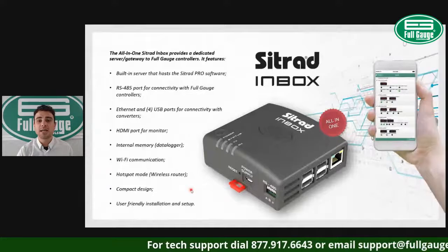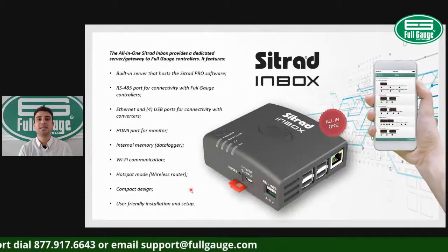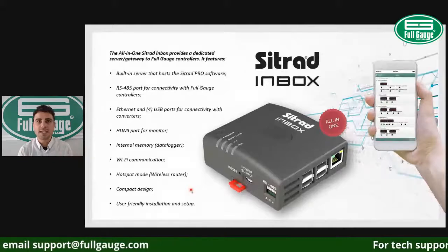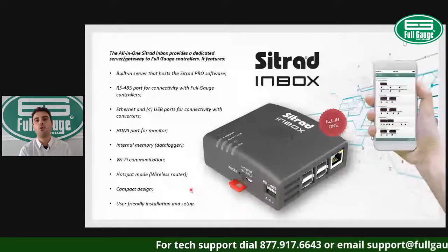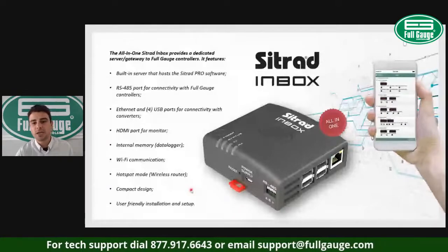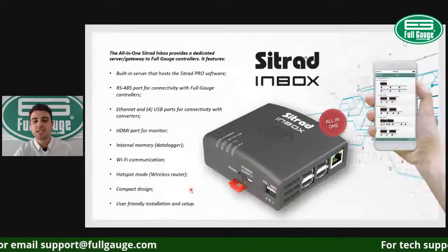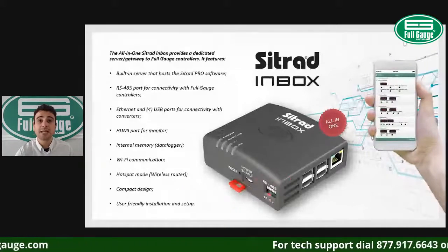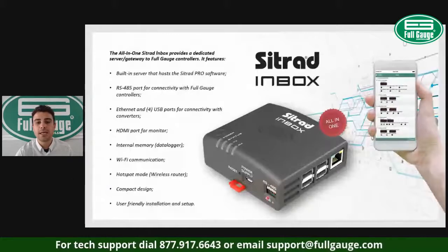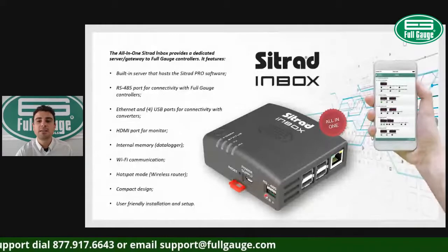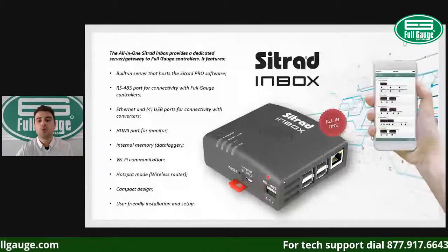The Sitrad Inbox will actually provide you a dedicated host and gateway to your Full Gauge controllers. So as you can see here, we've got the RS-485 port on the Sitrad Inbox, which you can connect. You can daisy chain up to 32 controllers to it and use the Sitrad Inbox as a computer plus Conv32.